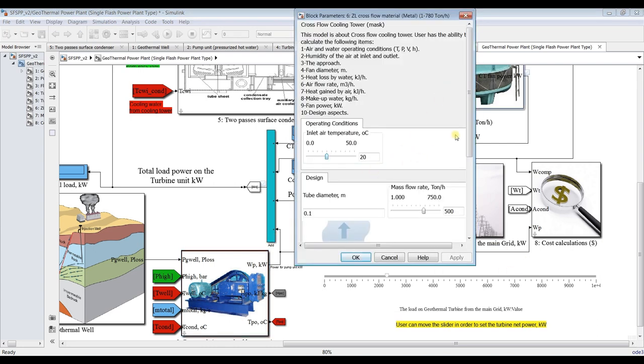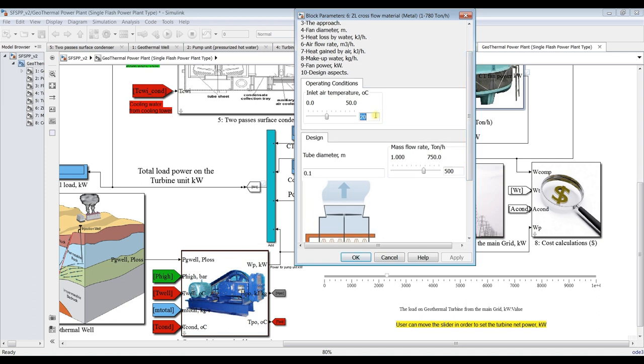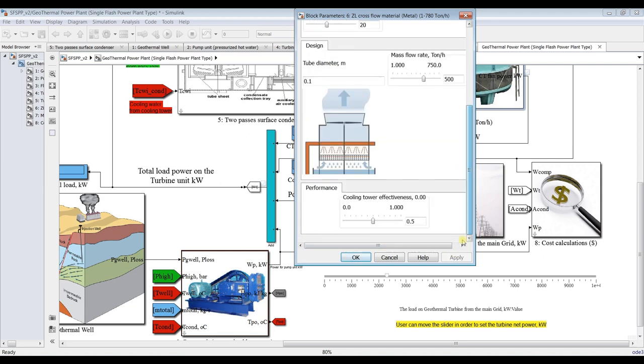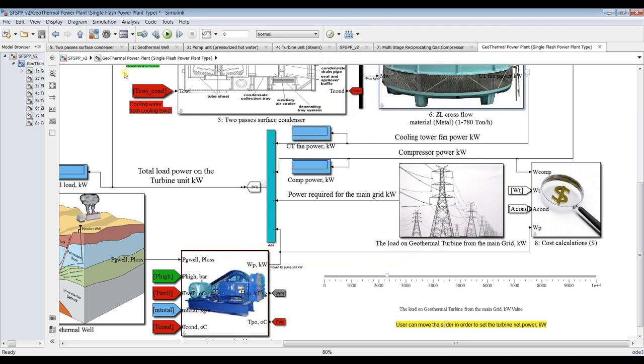For the cooling tower, assign the air temperature used to cool the condenser stream, and the mass flow rate through the cooling tower — this parameter determines the number of units needed. If you lower the mass flow rate, you need more units. About 500 tonnes per hour is quite good — meaning I'll use two units. Effectiveness for such configurations is typically between 0.4 and 0.6.